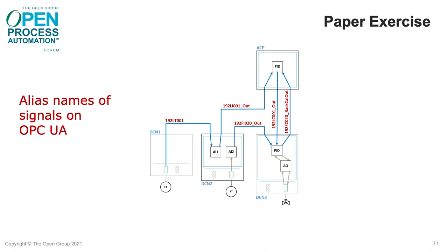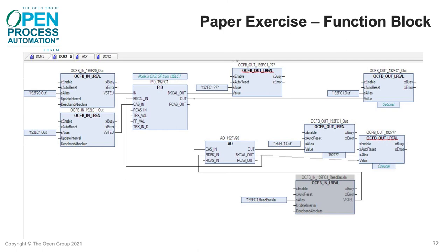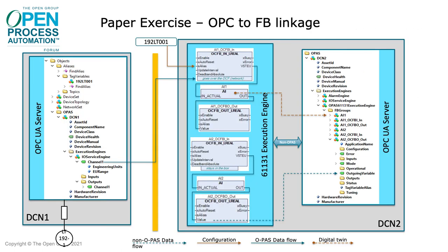We show how process values are communicated between control nodes via OCF, giving each signal an alias name that can be looked up in GDS to find its physical location. Here is a subsection of the function block application to control this process, showing OCFB blocks to communicate between control nodes and a PID block to compute the control action. This slide shows how data within the various function blocks is mapped into the OPC server and the OPAS information model — the red line shows the representation of the execution engine running the function blocks, the purple is the instance of an OCFB block named AI2_OCFB0_out, and the yellow shows one of the parameters within that block being mapped to the outgoing variable OPC item.